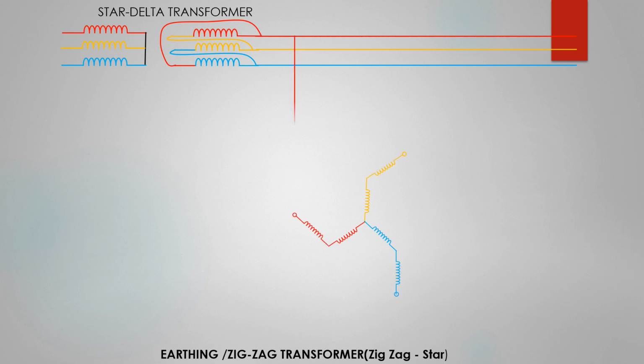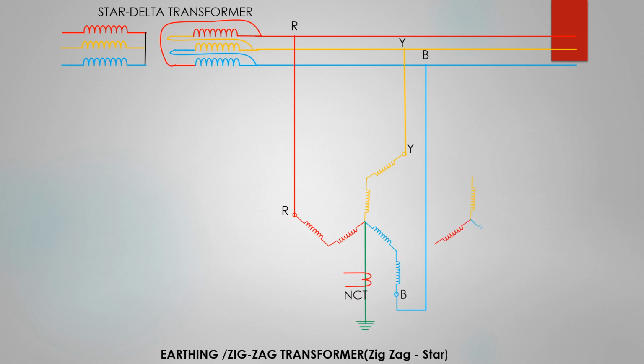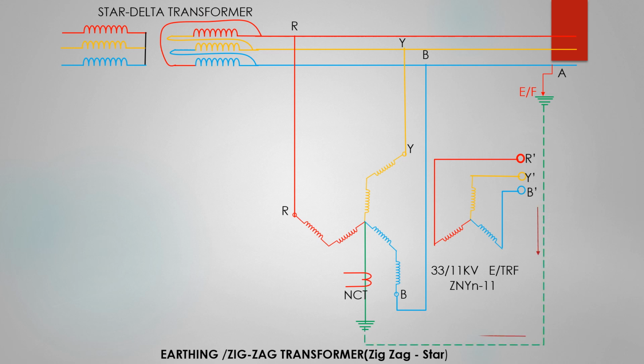A zigzag transformer with zigzag primary and star secondary has been connected with the bus RYB. The neutral has been earthed through the primary of an NCT, neutral current transformer. And now the earth fault current's return path has been established. Suppose an earth fault occurred at point A of B phase. The earth fault current finds a return path through the NCT to the neutral point of the zigzag primary and completes its return path.